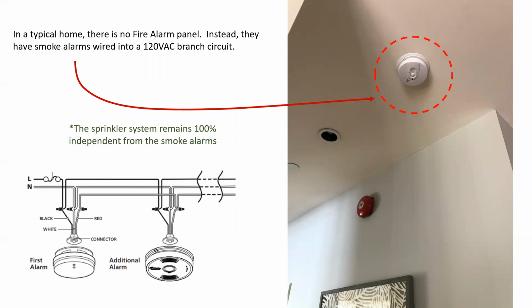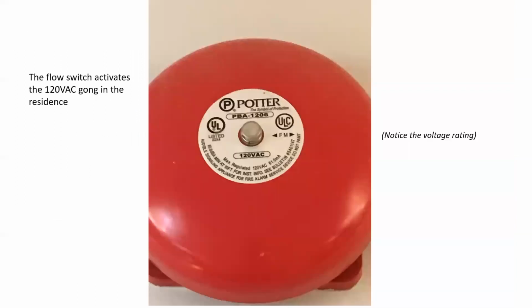The sprinkler system remains 100% independent from the smoke alarms. And we can see it has a separate notification device, a gong. The flow switch activates the 120 volt AC gong inside the residence. And notice the voltage rating, which would be somewhat uncommon in most fire alarm installations.